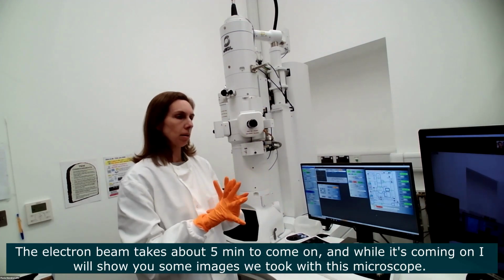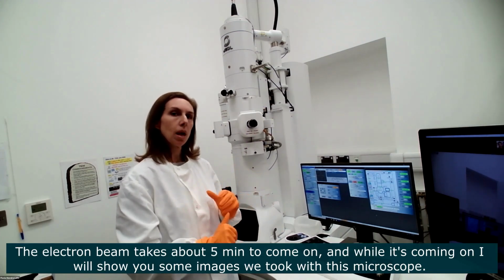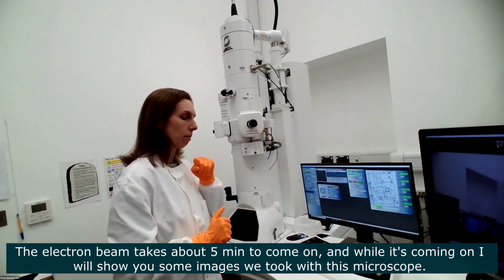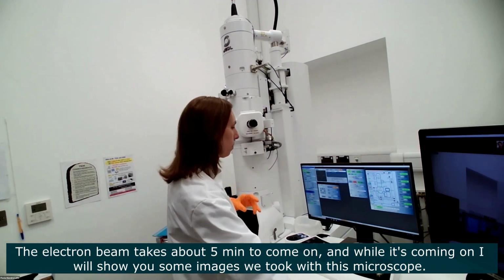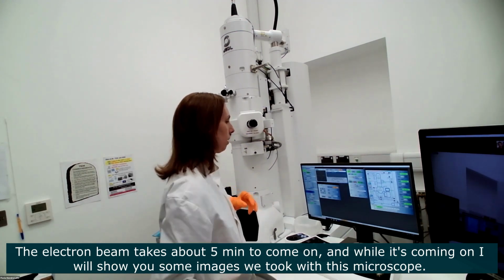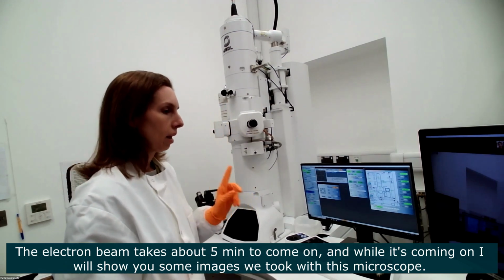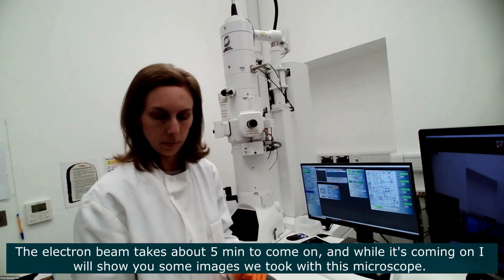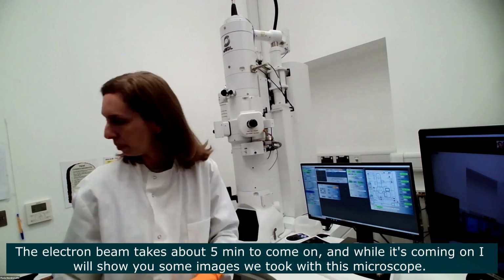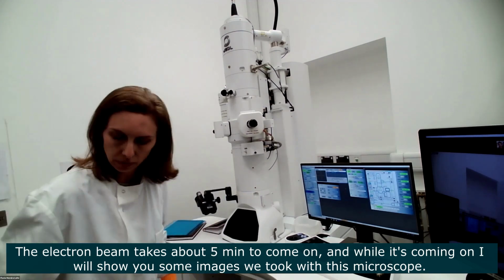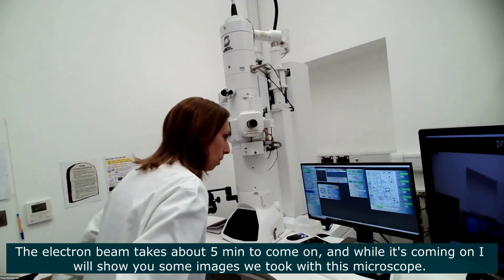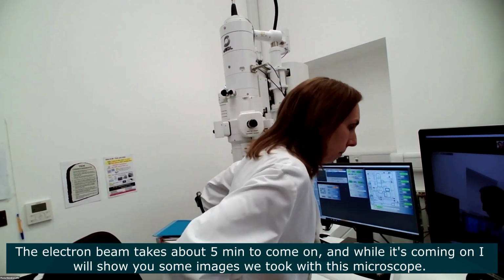The electron beam takes about 5 minutes to come on, and while it's coming on, I will show you some images that we've taken on this microscope. Now we can start the filament on. That's the second position.